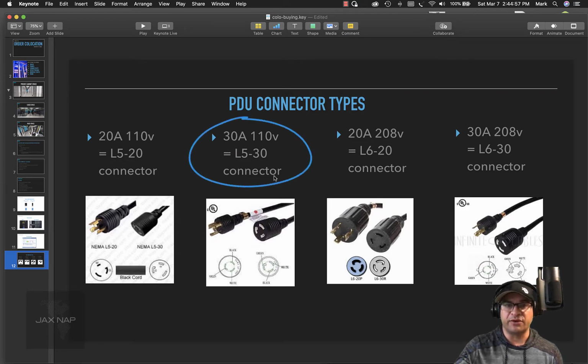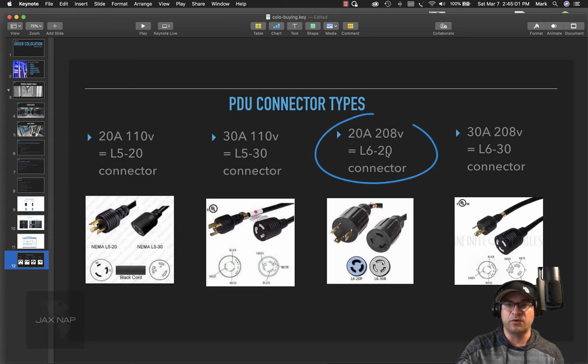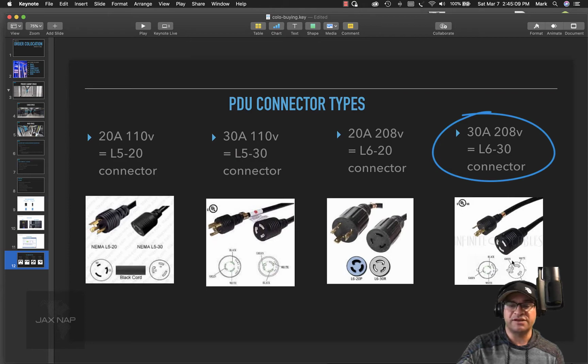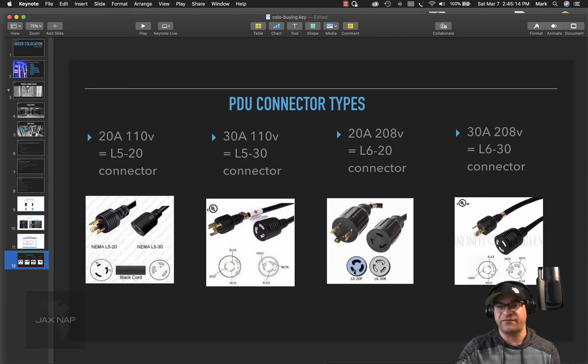You also have a 30 amp 110, which is an L5-30 connector. A 208 volt is an L6-20 connector, and a 30 amp 208 is an L6-30 connector. So just take a look at the bottom of the screen over here, and if you get a chance, go ahead and Google it. Just figure out exactly what the connection looks like.